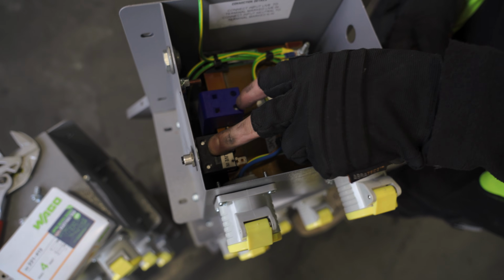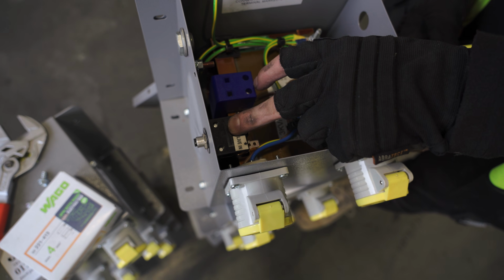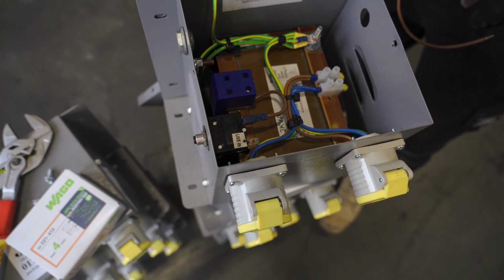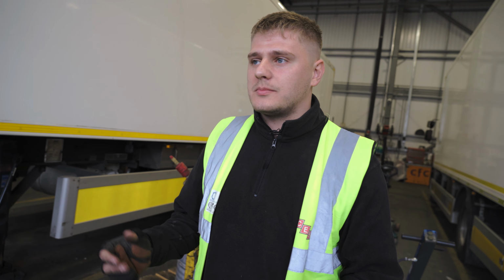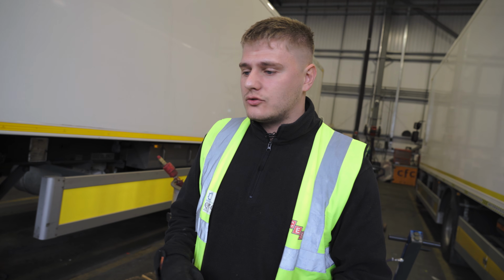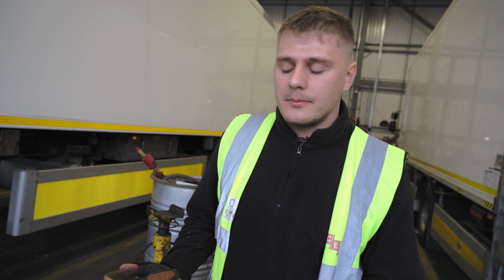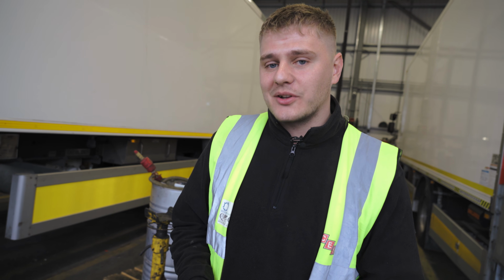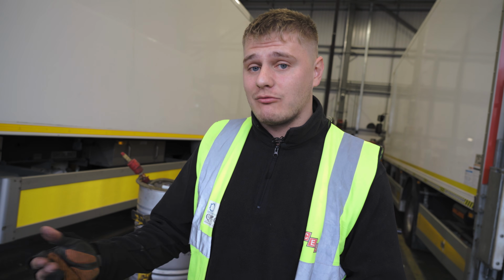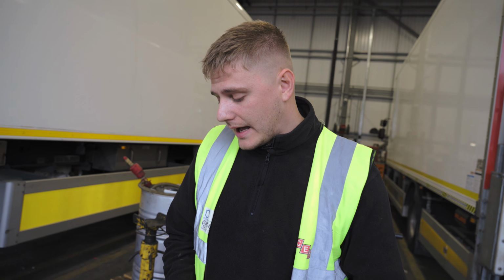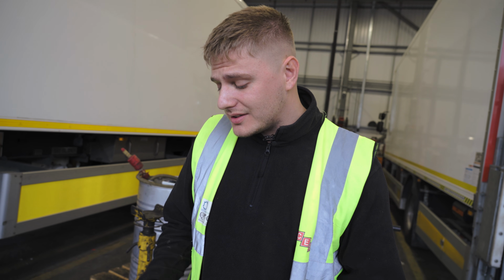This thermal overload is actually quite forgiving. You can overload it at about 150, 200% and it will last about an hour. After that, it drops right down to like 5 seconds trip time. So yeah, you don't want to go too far with it. It's designed to be ran at overload sort of currents if need be.